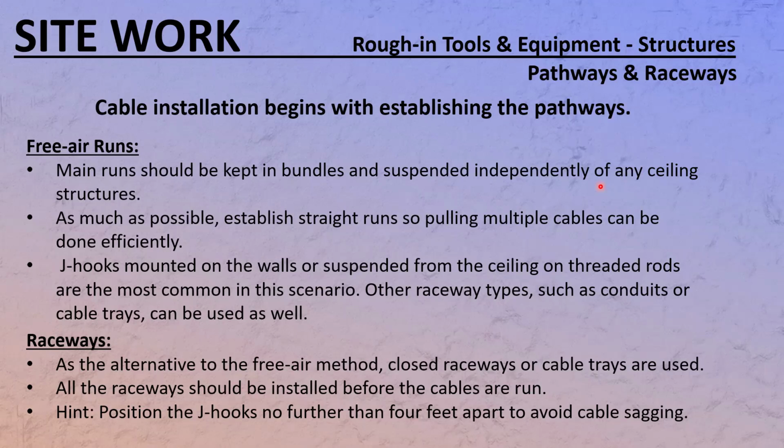So the reason for that is any wiring should have independent suspension to the red iron, and I'll show you what the red iron is, or to the walls, but not to any kind of structure, especially not the structure that is holding the ceiling tiles.